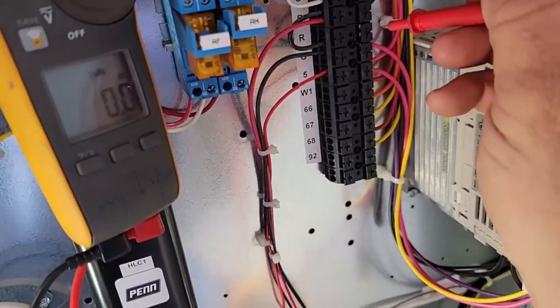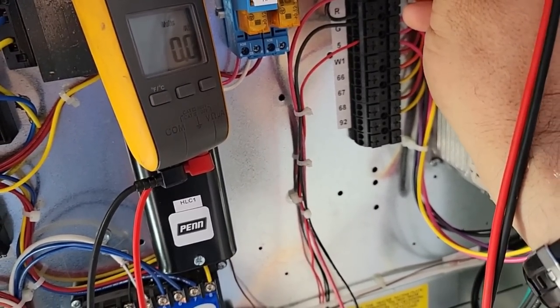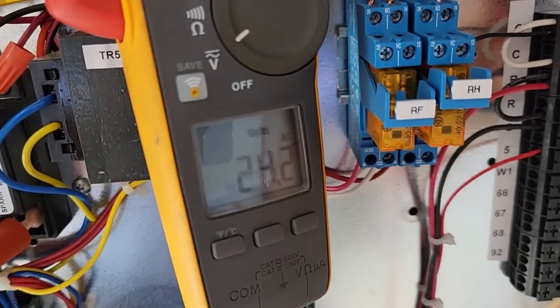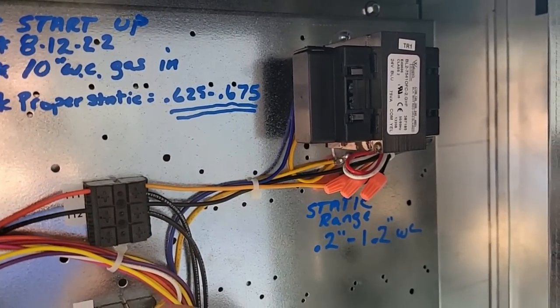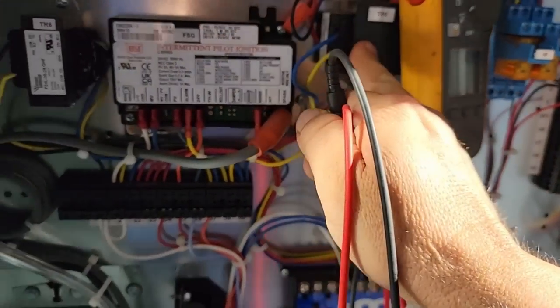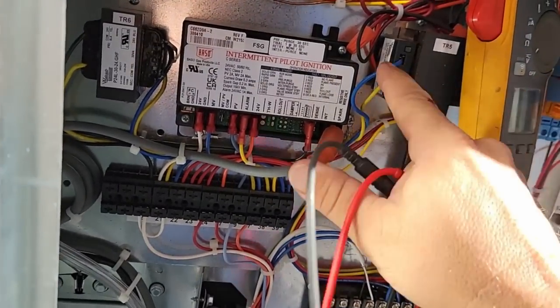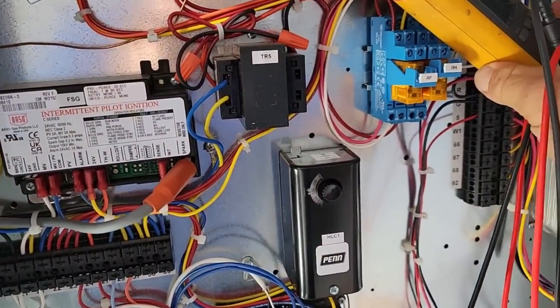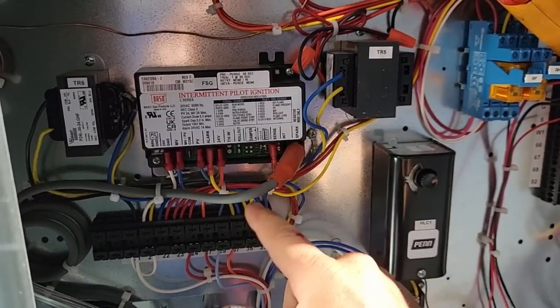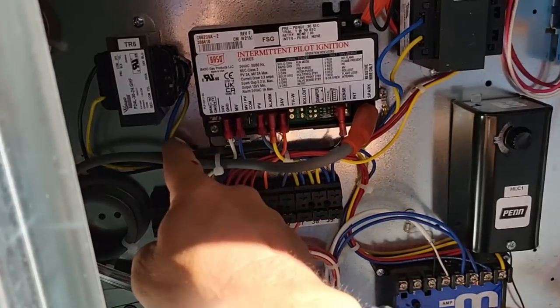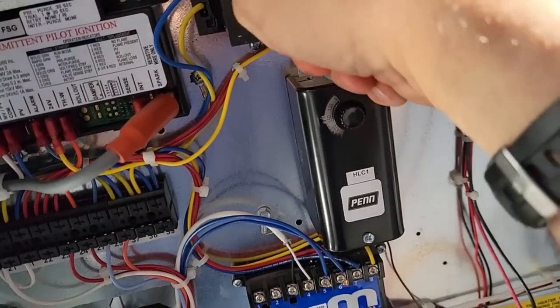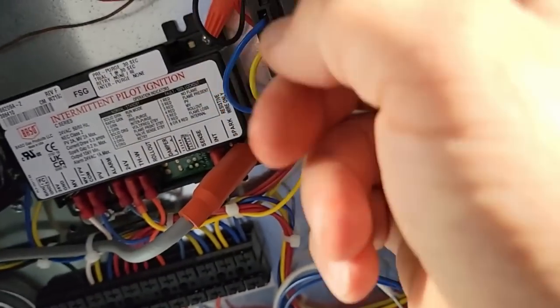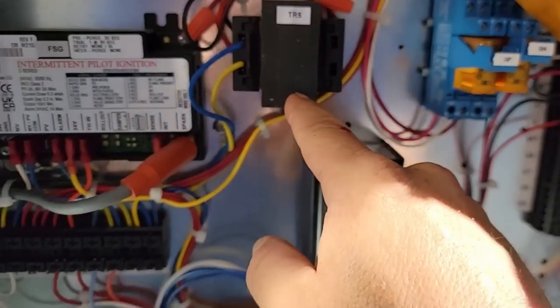Wanted to check our power here on common and R, which we have 24 volts. So it appears we've got that wired right. We also have a transformer over here. We have an isolation transformer, I believe, on one of these, because that was what I found out the last time. That one's not adjustable, and that one's not adjustable either, so it don't really matter.